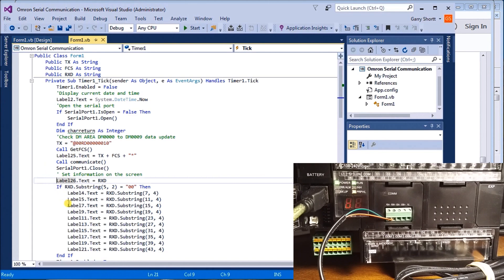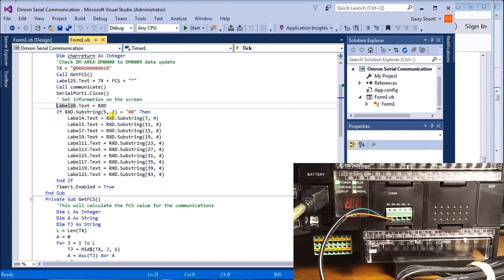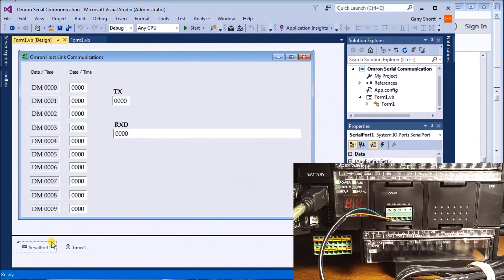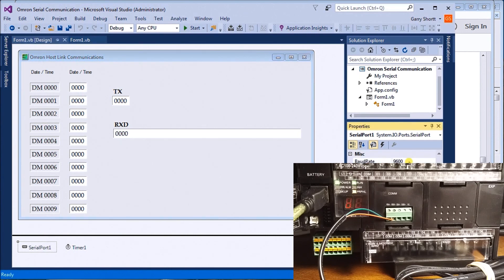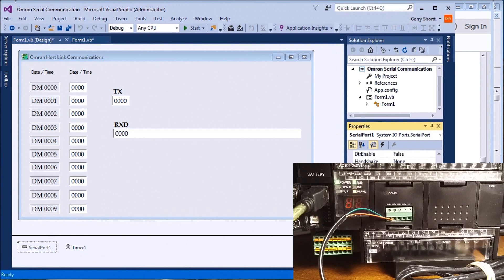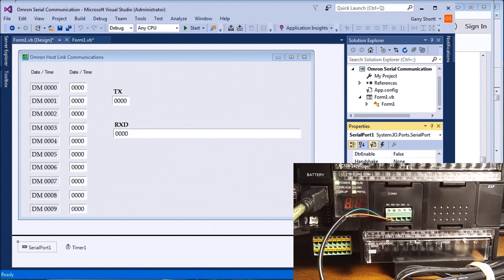We label the response — the RXD data coming back from the controller — then split that information and populate the registers shown on the main form screen. Finally we re-enable the timer so the whole process starts again. Looking at the serial port properties, everything is set to the OMRON defaults: 9600 baud, 7 data bits, even parity, two stop bits, communicating on COM port 5.